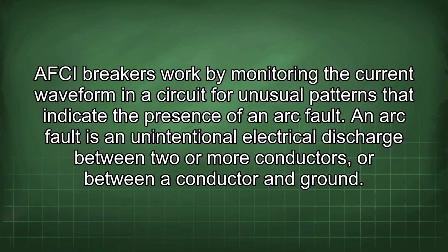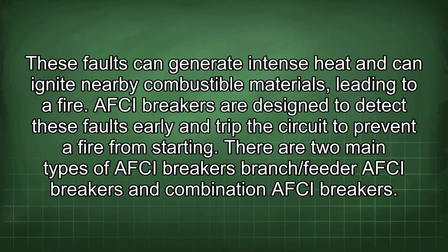AFCI breakers work by monitoring the current waveform in a circuit for unusual patterns that indicate the presence of an arc fault. An arc fault is an unintentional electrical discharge between two or more conductors, or between a conductor and ground. These faults can generate intense heat and can ignite nearby combustible materials, leading to a fire. AFCI breakers are designed to detect these faults early and trip the circuit to prevent a fire from starting.